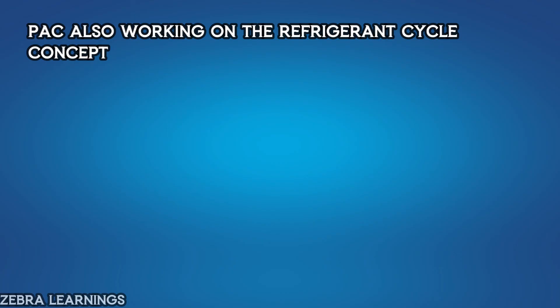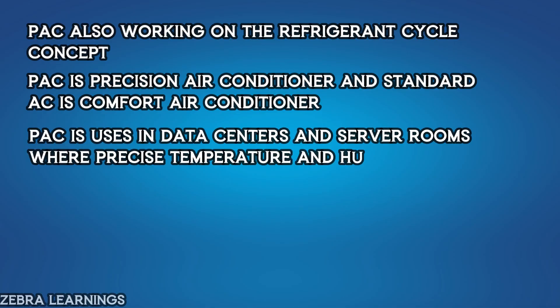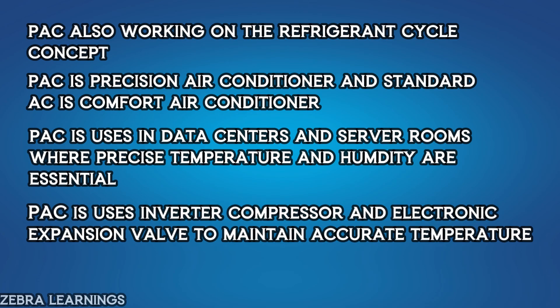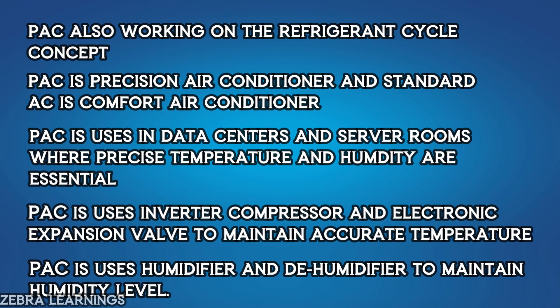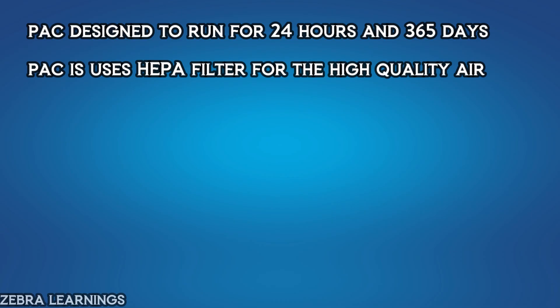Like the air conditioners we use at home, PACs also operate based on the refrigeration cycle concept. PACs are often referred to as precision air conditioners, while standard air conditioners are called comfort air conditioners. PACs are primarily employed in environments where precise temperature and humidity control are essential, such as data centers and server rooms. To achieve accurate temperature regulation, PACs often incorporate inverter compressors and electronic expansion valves. Humidity control is achieved through humidifiers and dehumidifiers. PACs are designed for continuous operation, capable of running 24/7 throughout the year, and employ high-quality filters such as HEPA filters to remove particles as small as 0.3 microns from the air.